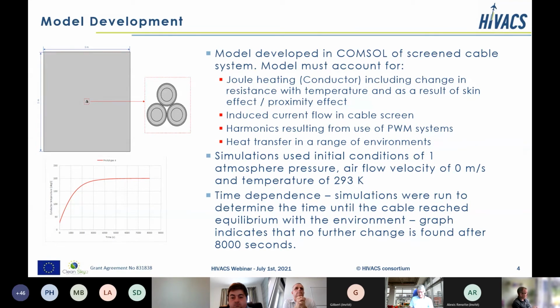Within a pulse width modulated system, of course, you may expect fairly significant levels of harmonics in the current. So while the current might be quite sinusoidal, it will likely have third, fifth harmonic frequencies. And then, of course, finally, you've got to understand heat transfer. So the passage of the heat from the conductor across the insulation and into the air itself.